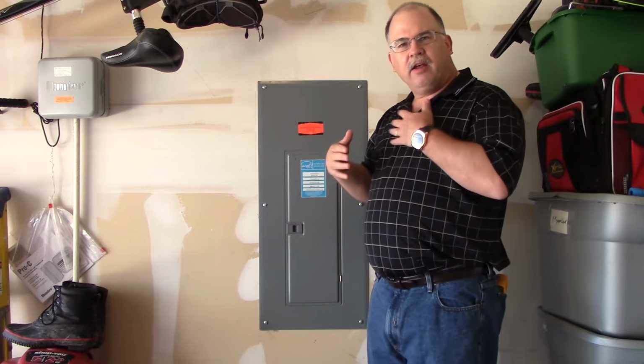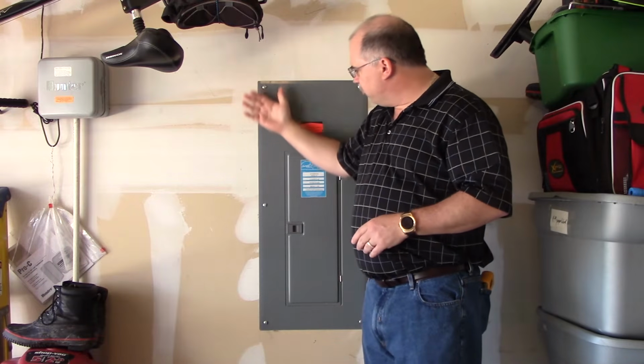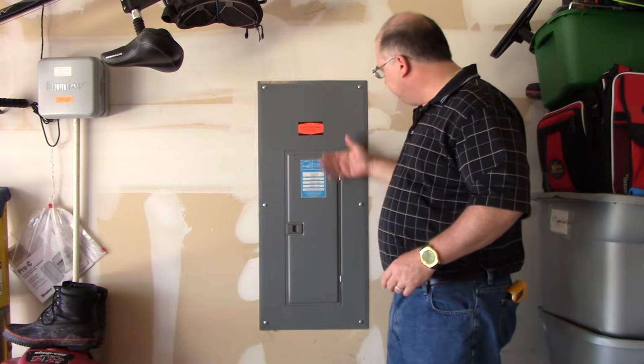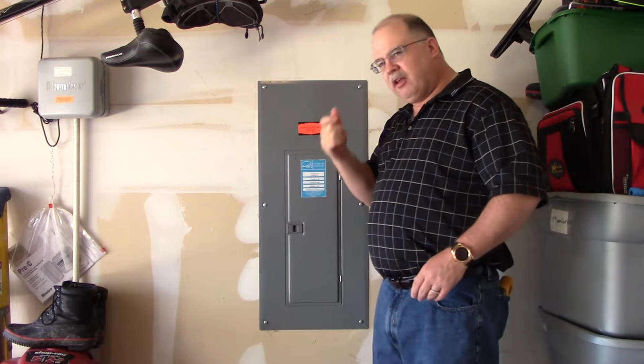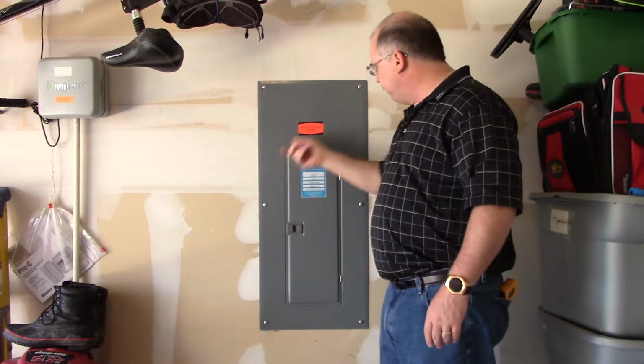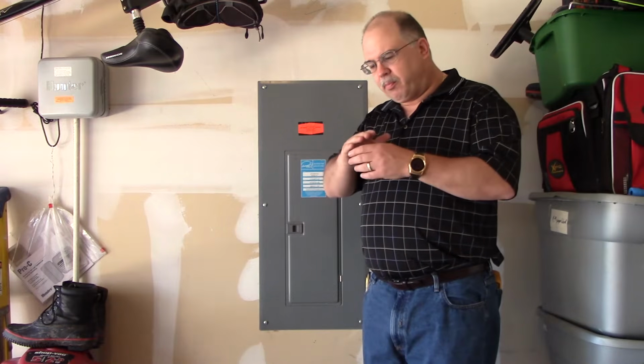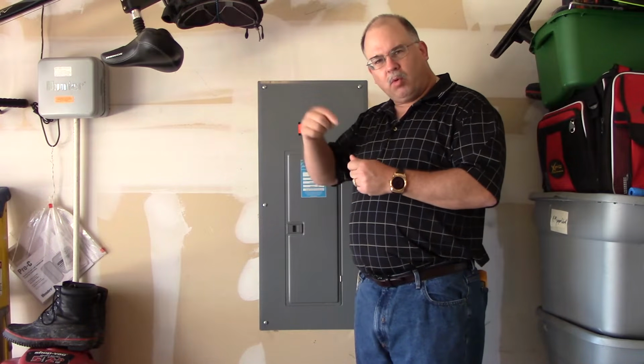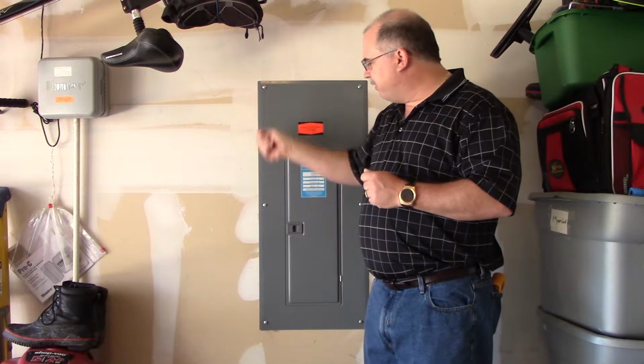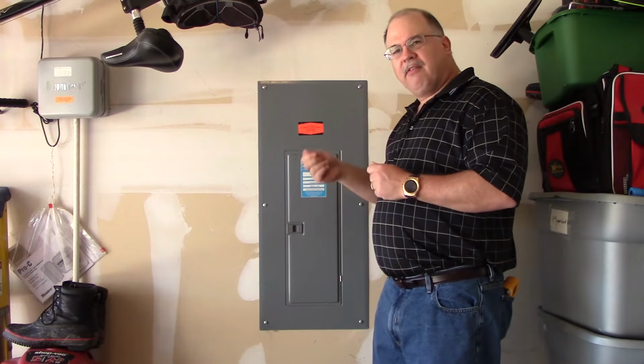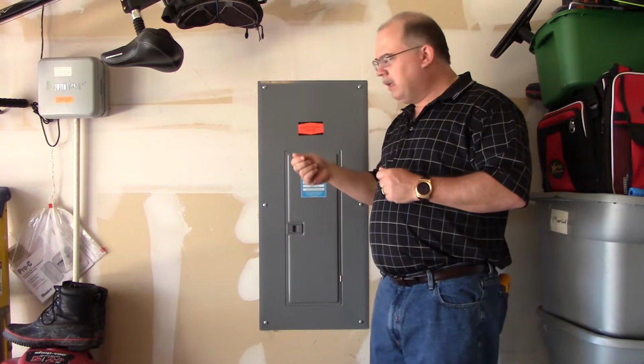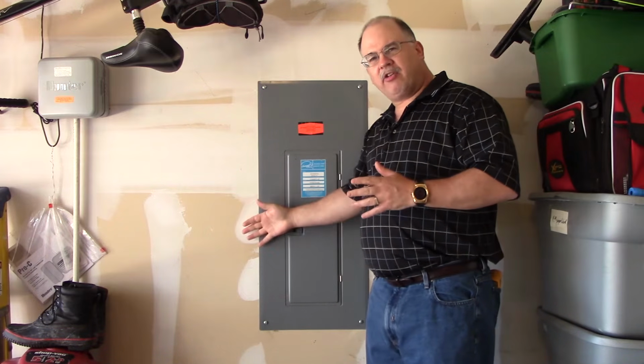So we're going to use the back of our hand that is furthest from our heart, and we're going to check all the screws, run it along the cover to see if anything's hot or energized, that we might feel anything that's out of the normal. We can use a voltage ticker as well to test the screws, test the panel. Or again, we could use the old electrician's cheat method and use an extension cord with the prongs removed. The only thing you have is the equipment ground terminal on the extension cord so that you can plug it in a receptacle. You can bring it over here. You can take a voltmeter, put one end down in the slot for the equipment grounding conductor and take the other end of the voltmeter and actually test your screws and your panel and your hinges and everything like that using a voltmeter if you want to be sure. And then you're sure that this is totally not energized and it's ready to go.